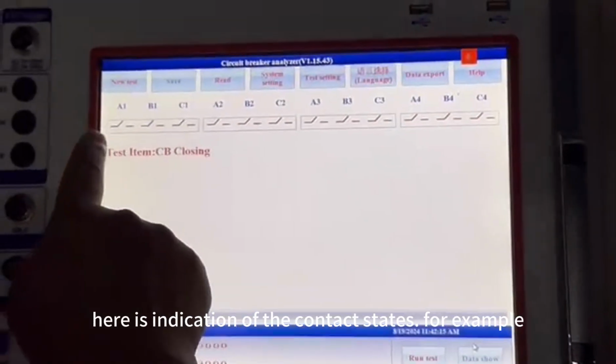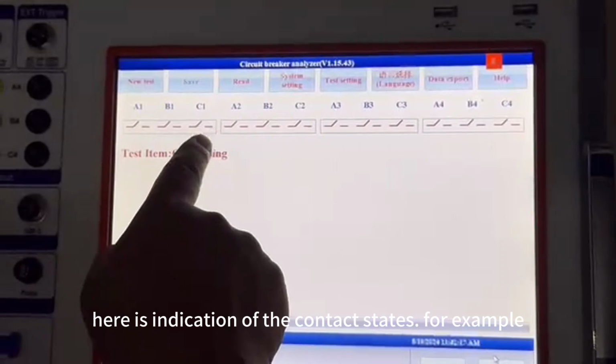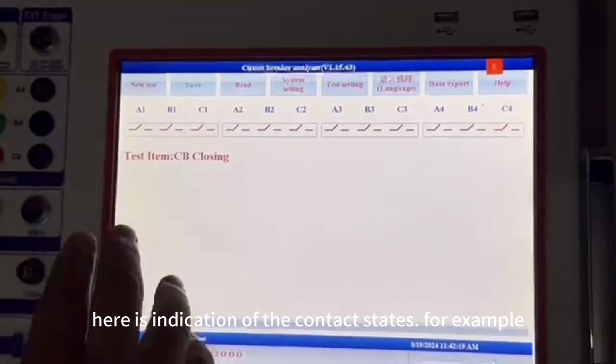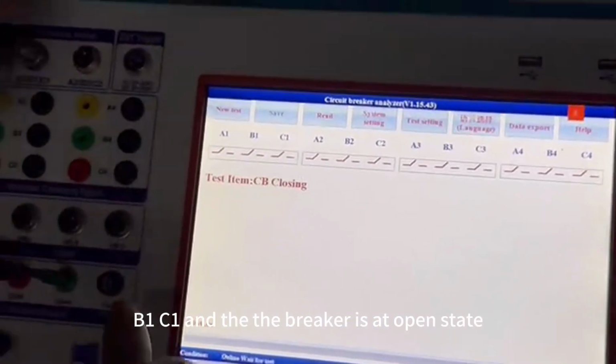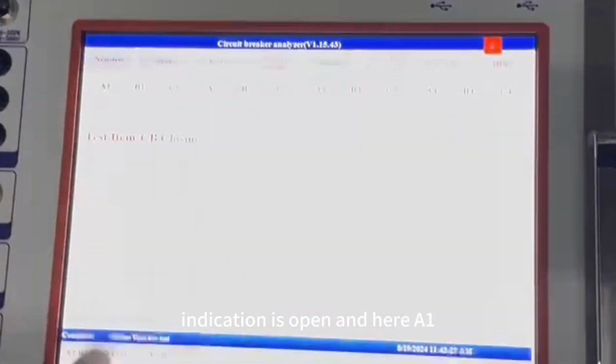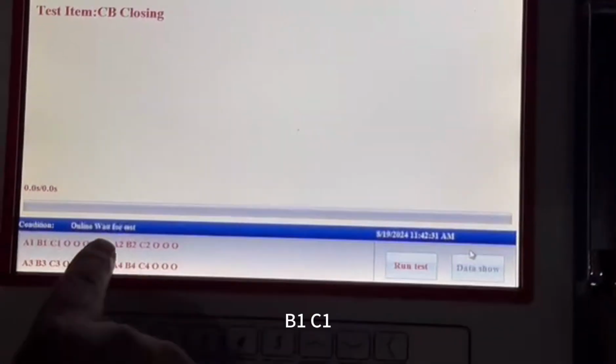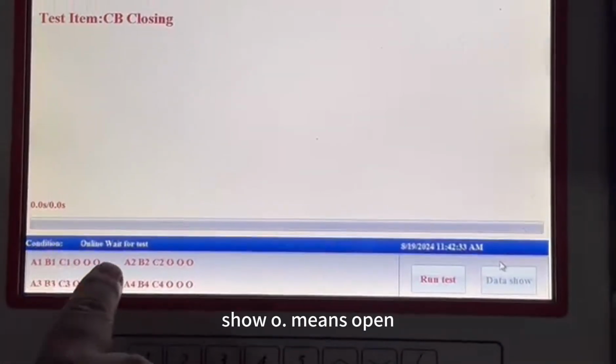Here is the indication of the contact states. For example, now we have connecting A1, B1, C1, and the breaker is at open state. So A1, B1, C1 should be open. The indication is open. And here, A1, B1, C1 shows O, which means open.